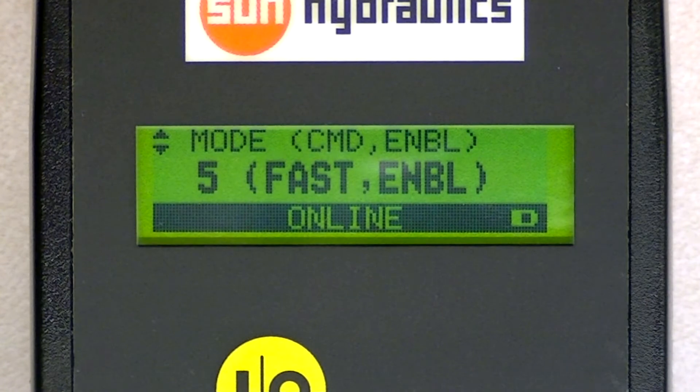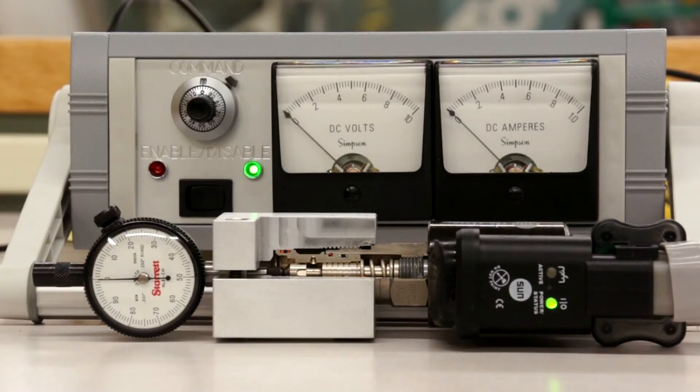The next mode is mode 5. Mode 5 is a 3-speed mode called fast with an enable. It is no longer proportional. The 3 speeds are off, the minimum output current that you set, and the maximum output current that you set.